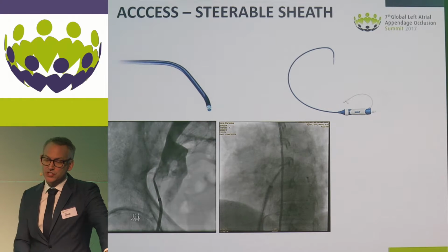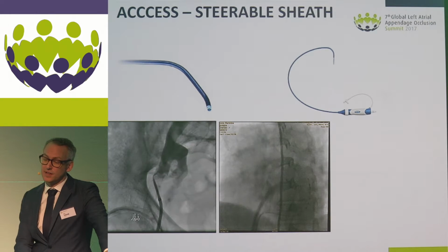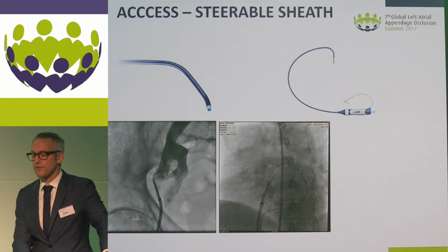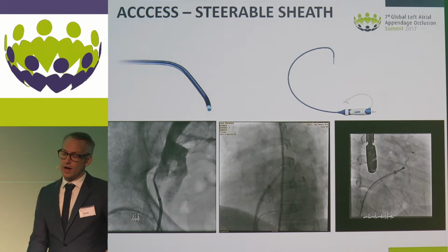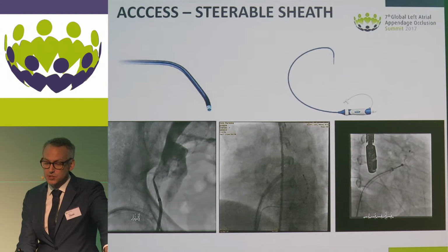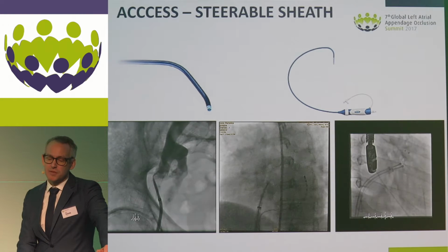And using this sheath, it has a 12 French inner diameter, as I said. You can at least implant devices up to 25 millimeter, as you can see from the next video. So it's a different patient, but the same sheath.